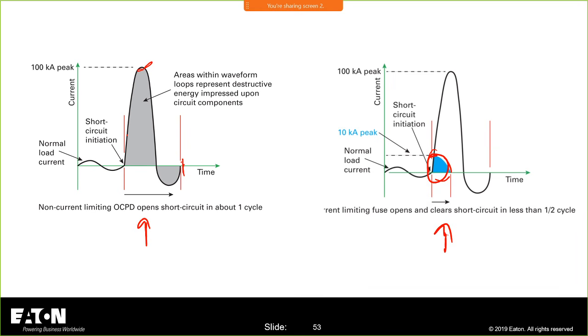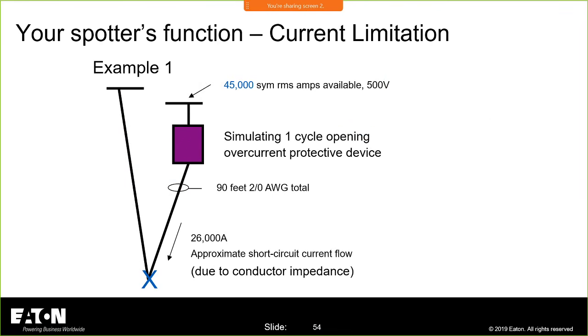I want that. And there's no better demonstration to show that and illustrate this important piece of the pie than to show the cable whip video. Now, what we do in this video is we take a length of 2-aught conductor, and if you've ever felt 2-aught conductor, you'll know it's not very flexible. It's a stiff conductor. I basically put 90 feet of that and I start with 45,000, but because of the impedance of the circuit, I'm really pushing 26,000 amps through this circuit.